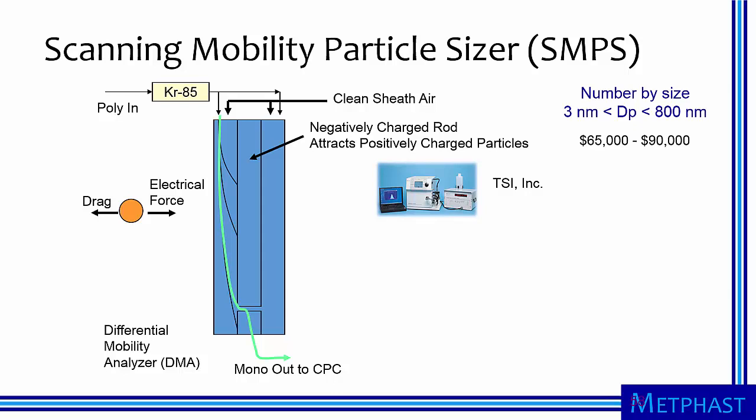The negatively charged rod attracts positively charged particles. Particles of one size pass through a slit in the lower section of the collection rod and are counted with a condensation particle counter, or CPC. This device can be used to measure particle number concentration by size from 3 nanometers to 800 nanometers.